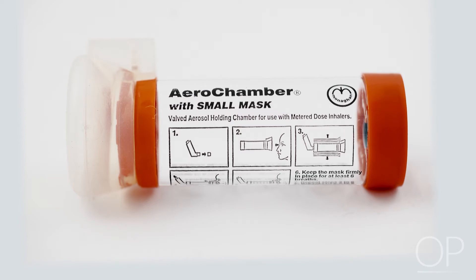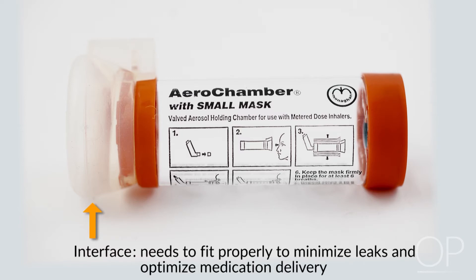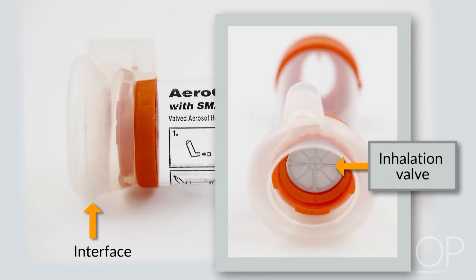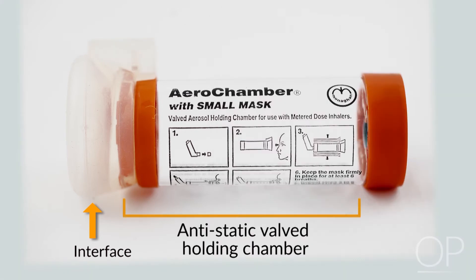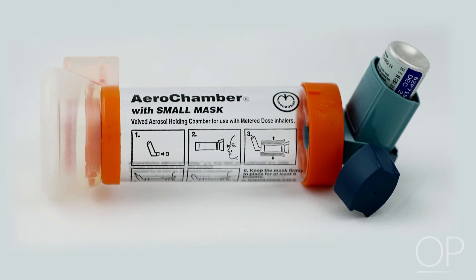Some components of the chamber itself: the interface — an appropriate sized interface is essential to minimize leaks during use and optimize delivery of our medication. The one-way inhalation valve separates the chamber from the patient and ensures that upon inhalation, the patient draws gas through the chamber that contains the medication. The one-way exhalation valve ensures that upon exhalation, gas is diverted through a separate channel out to the room and away from the medication chamber, helping to prevent dilution of the medication from exhaled gases. The antistatic chamber and the MDI adapter — the MDI adapter is where the chamber interacts with the MDI and is able to accept medication.